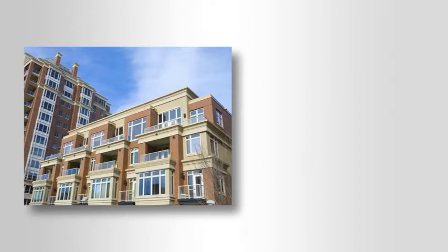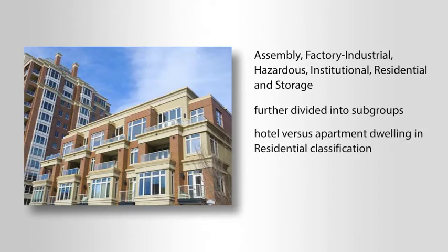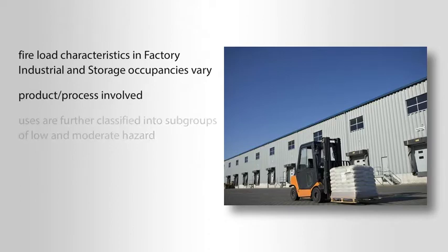In addition to these major classifications, the occupancy groups of assembly, factory industrial, hazardous, institutional, residential, and storage are further divided into subgroups in order to accommodate some variations in the hazards associated with the uses within each group. For example, a hotel versus an apartment dwelling in the residential classification. The fire load characteristics in factory industrial and storage occupancies vary considerably depending upon the product or process involved, and therefore these uses are further classified into subgroups of low and moderate hazard depending upon the potential fire severity.